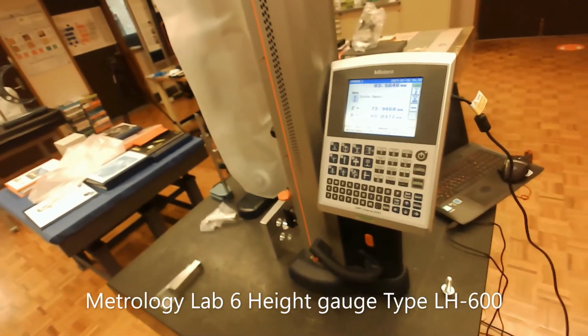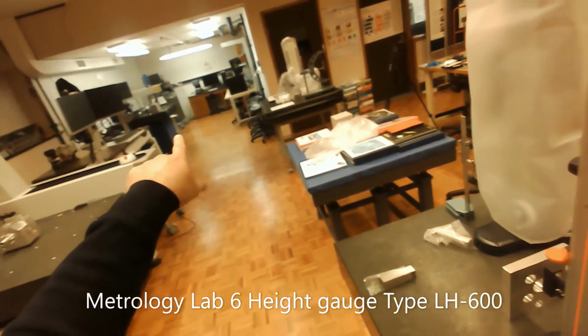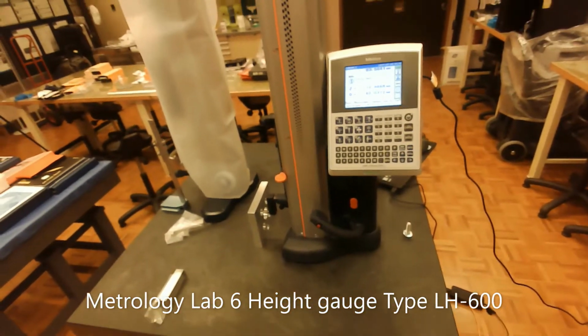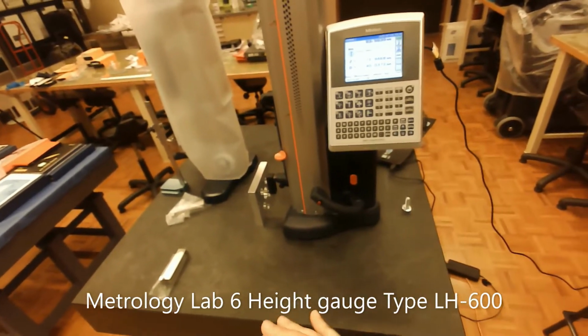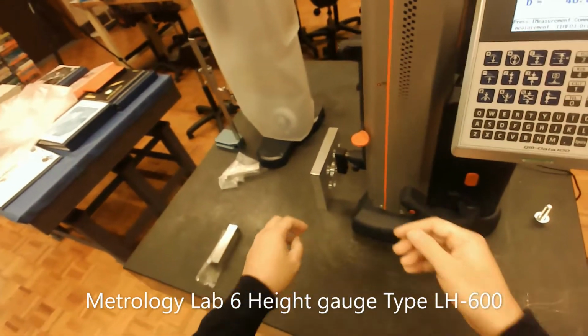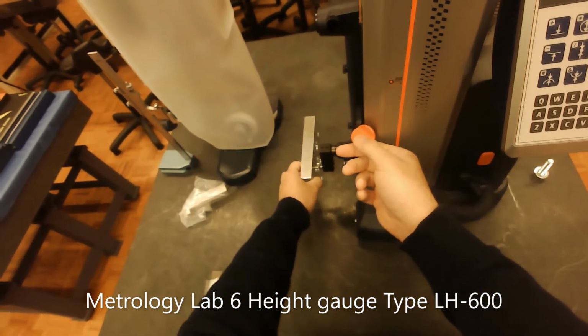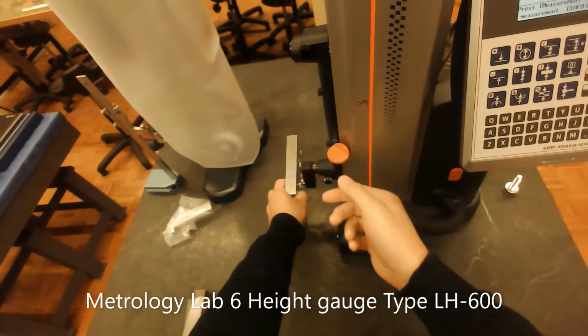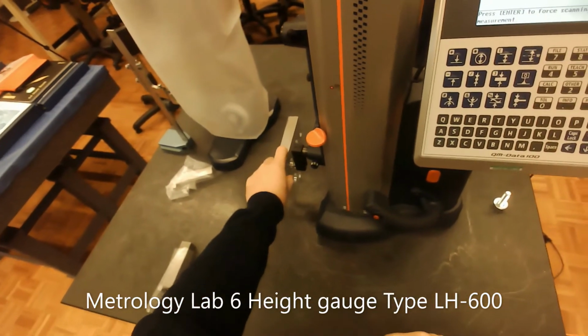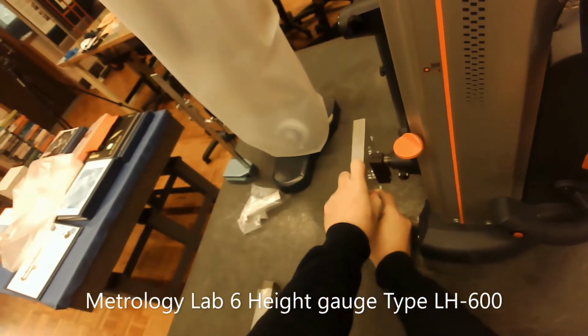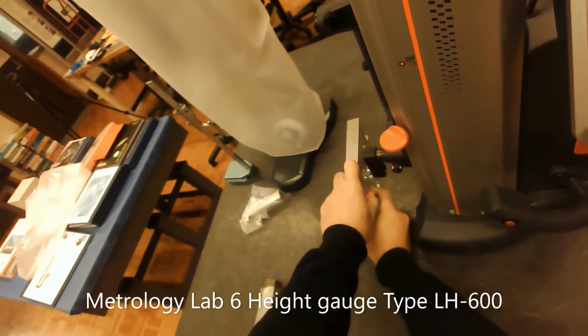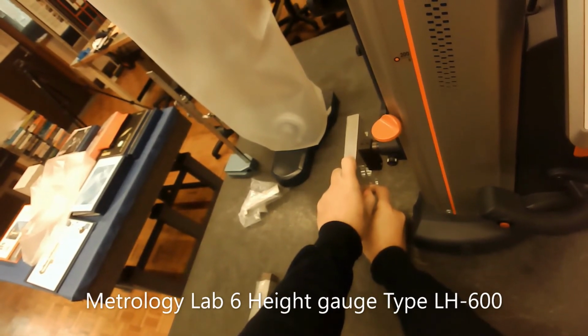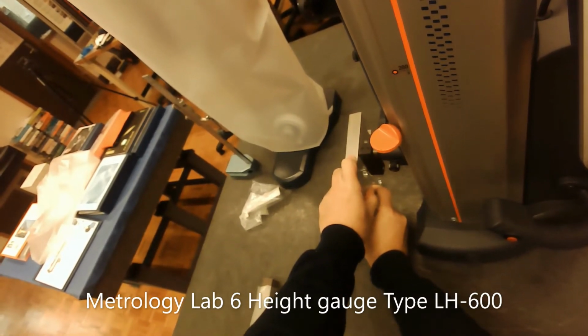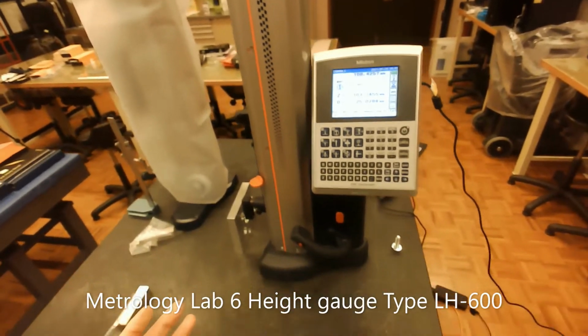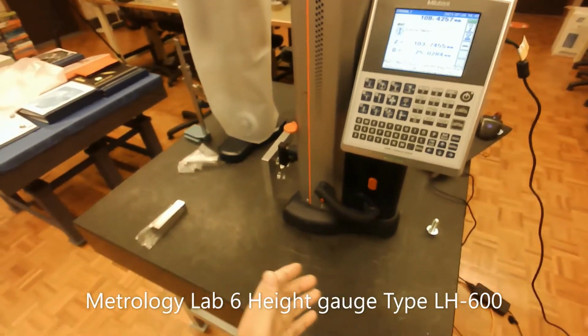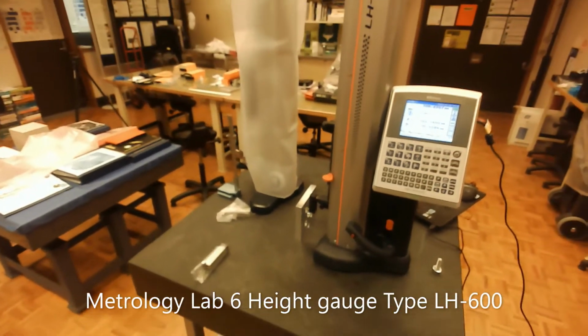Now, I'm going to take the same part to the machine there, which is called the CMM machine, or the coordinate measurement machine, and I will try to check the same diameter. So just remember this value is 40.3072. Now I will take the measurement for the other circle here using the same technique. So I'm going to put the probe here and press measure. It's going to go down, beep, pull it, push it, and this diameter is 25.0284 millimeters.